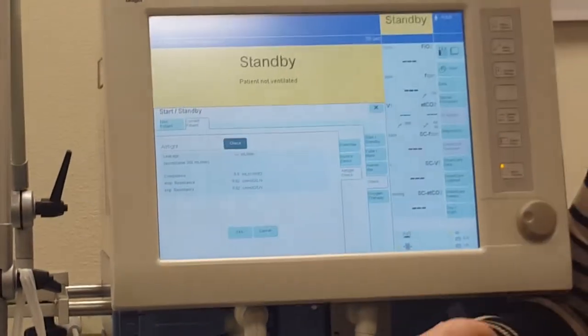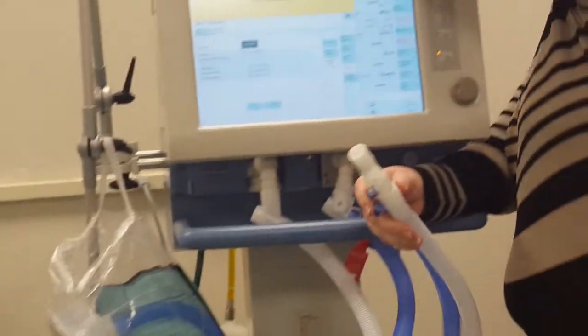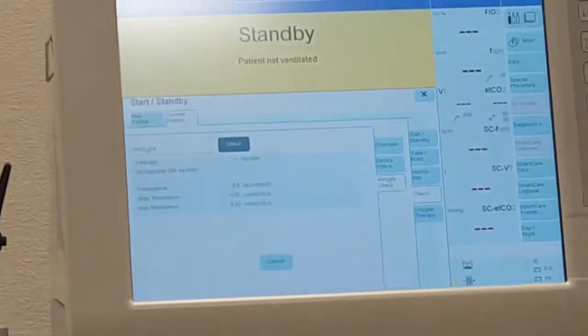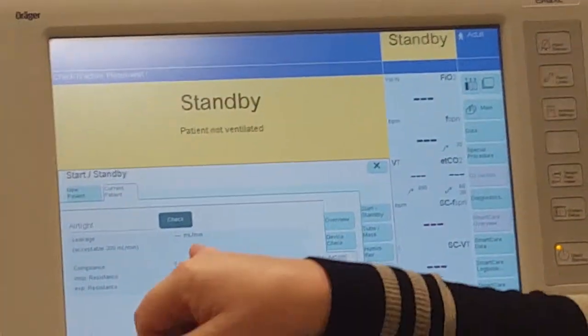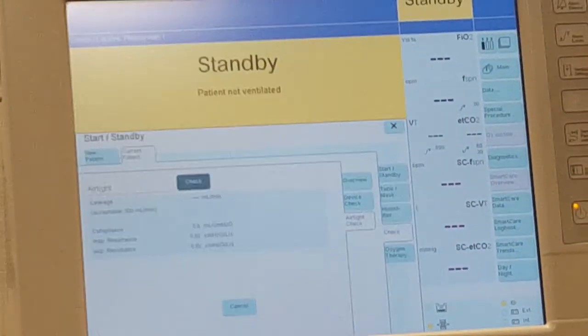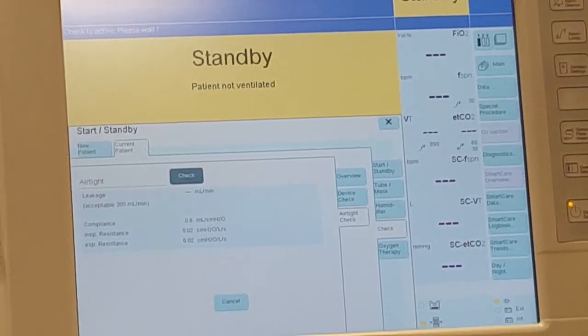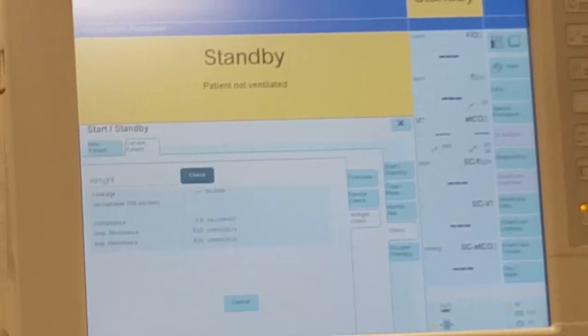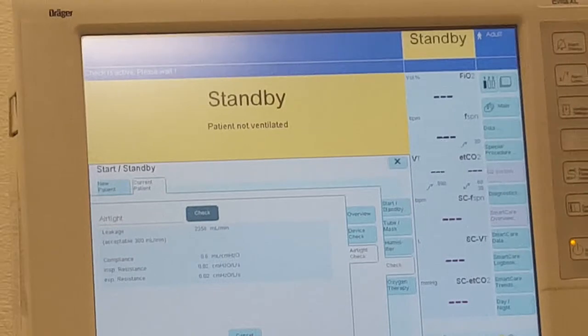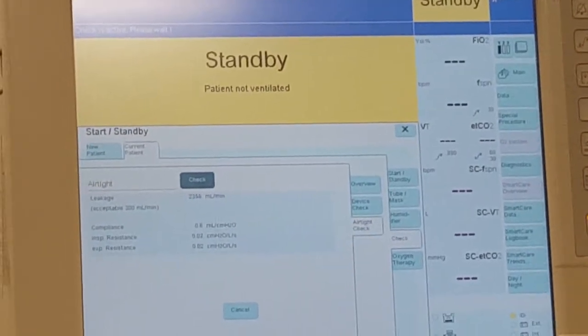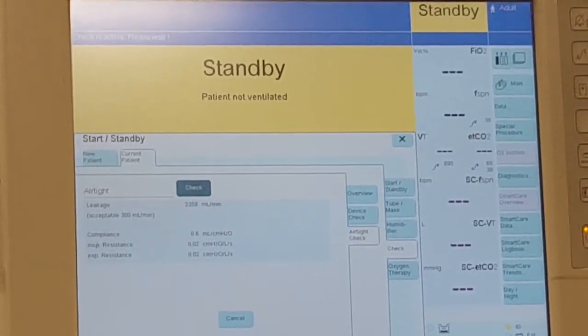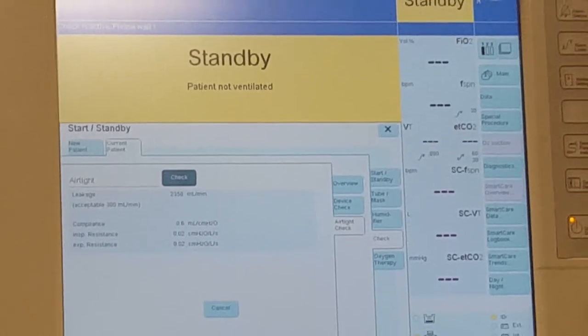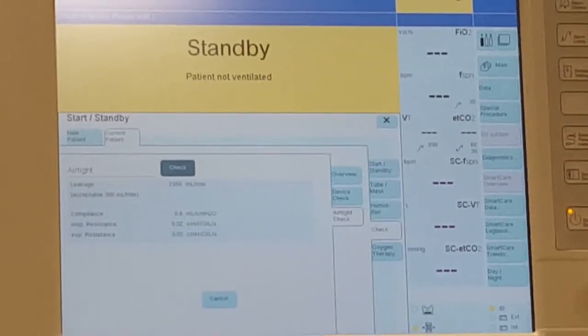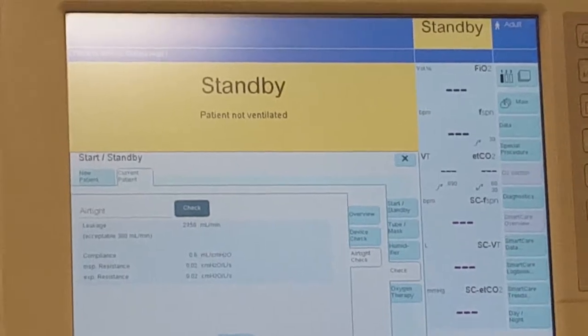Seal Y piece, confirm with yes. So let's just do this. I'm going to open this port. I'm going to seal my Y piece and I'm going to hit yes. Now you'll see what will come up here on the screen is really big numbers. 2,358 is what it says right now. And sometimes they'll fluctuate, but there'll be numbers in the thousands. That's telling you that there's a problem and there's a leak somewhere in your circuit.